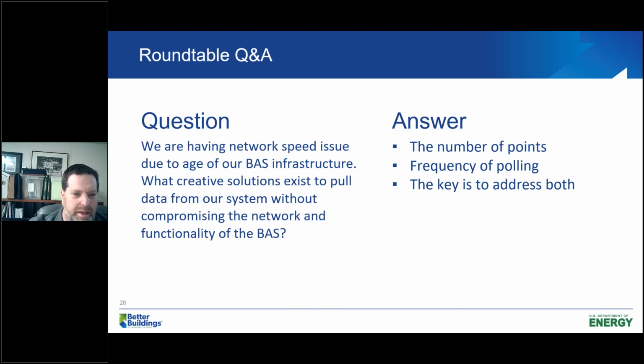Great, so this is not an uncommon thing. The key is addressing the number of points you're monitoring and the frequency of those points. For example, if you're polling every 5 minutes, can you poll every 15 minutes? I'm not talking about all points necessarily, but a smart EMIS provider can determine which points need it. Do you need all points polled at the same frequency? If terminal devices make up 75% of the points you're polling, do you need them all at the same frequency as the air handlers or plant equipment? Maybe you can poll those every 30 minutes. There's a limit to how far you want to go though, because the analytics don't work as well, so I'd say 15 to 20 minutes, 30 minutes at the longest, because you'll lose some granularity. Or if you have a command point and a feedback—a signal and a position point—do you need both to verify the feedback? Maybe you could just take the signal point.